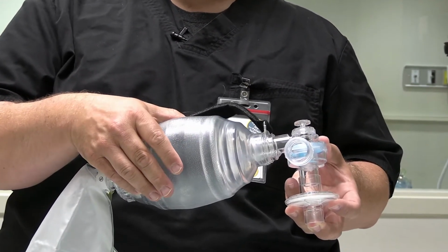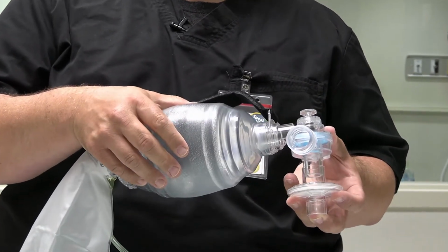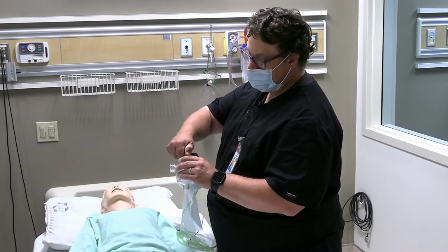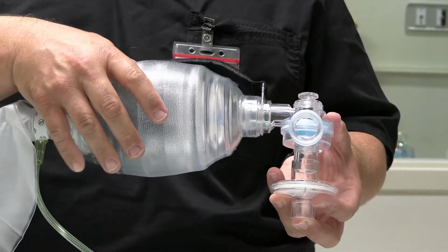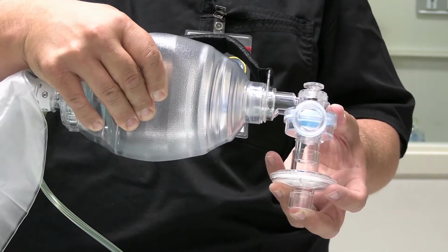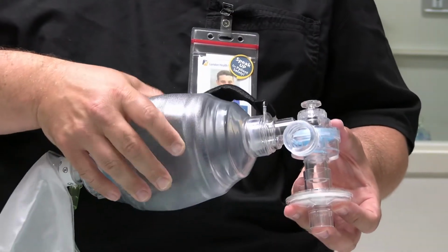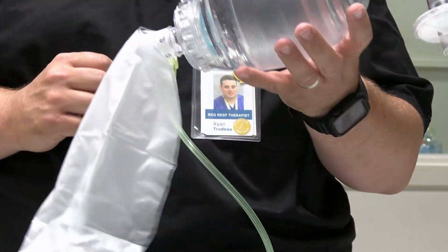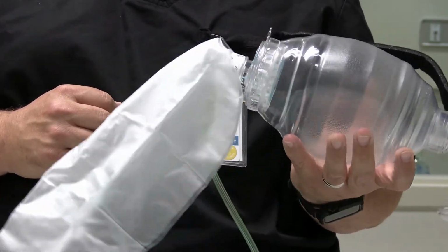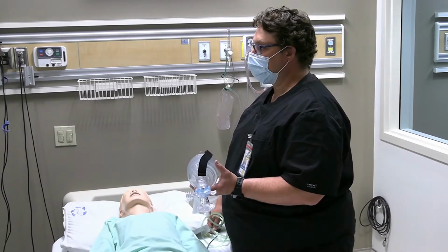Okay. So that will pop off when the pressure level gets to 40 centimeters of water, and you'll hear that there. The next one is to lock the pressure or close the pressure pop off. So the pressure pop off is now closed, and all you want to do is squeeze the bag to see that it's maintaining pressure, and it is. Okay, so that's your third test. You're going to open that, make sure your pop off pops off again, and then your third test is just to squeeze the bag and make sure it reinflates. So those are the 3 steps that you want to perform as you're testing your self-inflating bag.